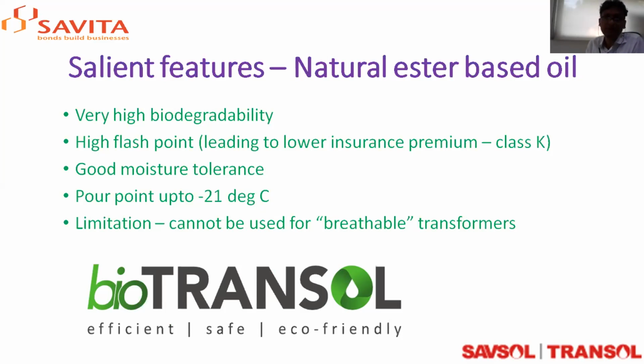It has a very high flash point and fire point, which allows it to be classified under class K. By classifying your transformer under class K, the insurance premiums you need to pay go down. This is a big advantage, not just in terms of the assurance and safety of a high flash point, but also in long-term cost benefit, since insurance premiums are a recurring cost—reducing them gives you the advantage of lower cost over a longer period of time.